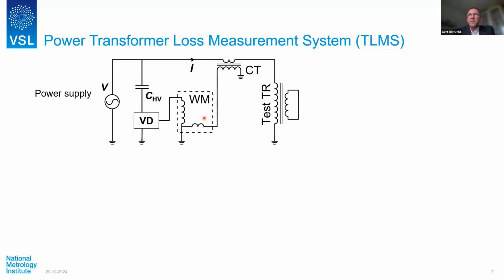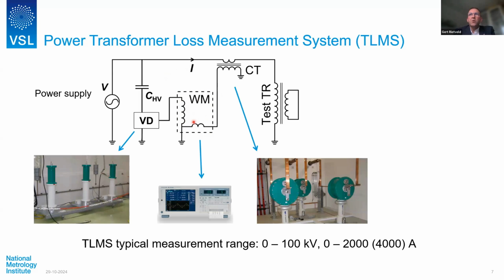that can be handled by sampling wattmeters. The sampling wattmeter that Ilya showed in itself already has voltage and current scaling. So this is additional current and voltage scaling in order to allow the measurement of the very high voltages and high currents that are applied. And to give you a certain impression about typical equipment that is being used, here the voltage divider on the left-hand side, where the high voltage capacitors are a key part, the sampling, digitizing power meters. There are many power meters on the market nowadays, and current transformers to scale the high current to the level that can be handled by this power meter. A typical measurement range is up to 100 kilovolts, up to 2000 or even 4000 amps, so very significant currents.